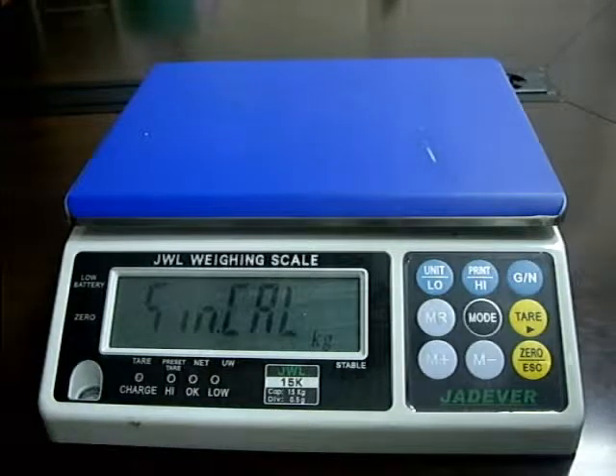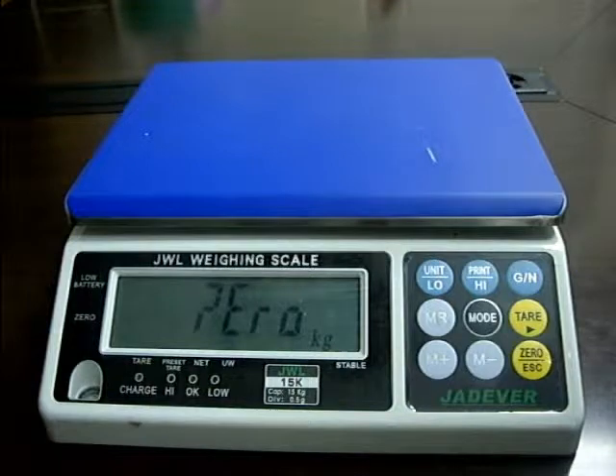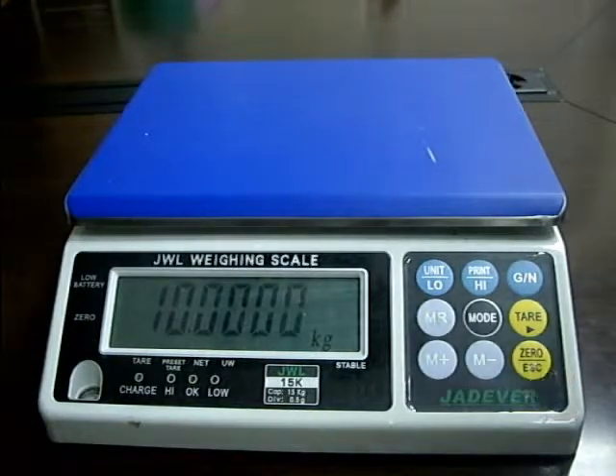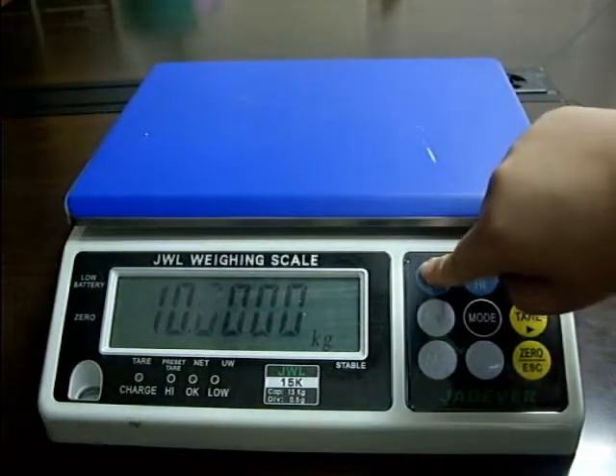Press key TARE to enter the zero point calibration mode. Wait until zero appears. Press key UNIT LOW to shift the words left, and key PRINT HIGH to shift the words right.